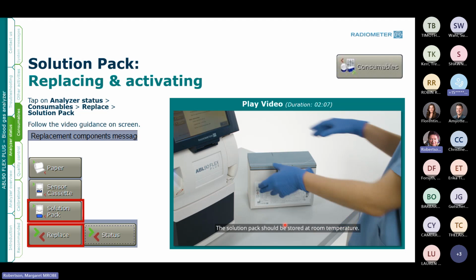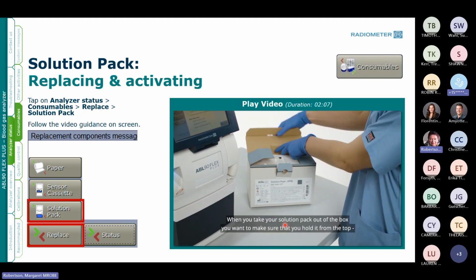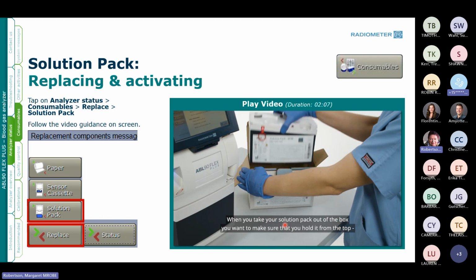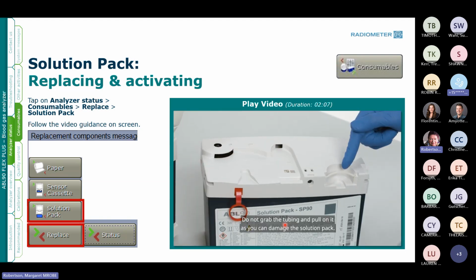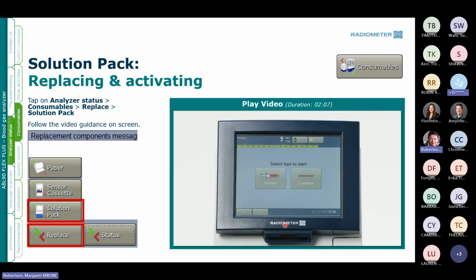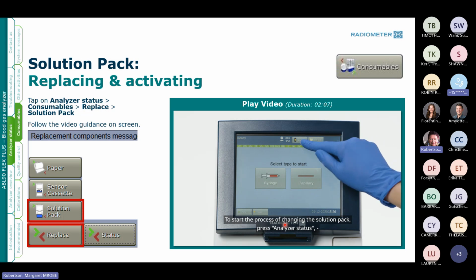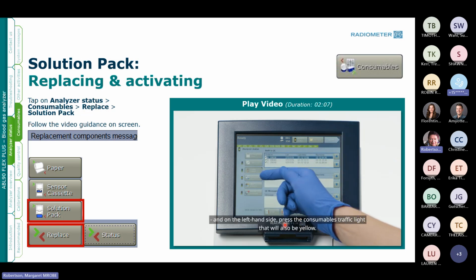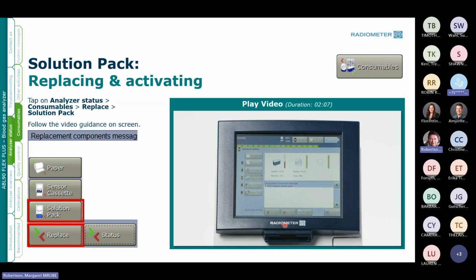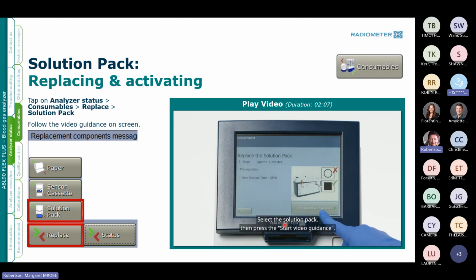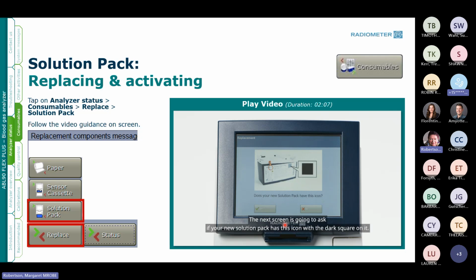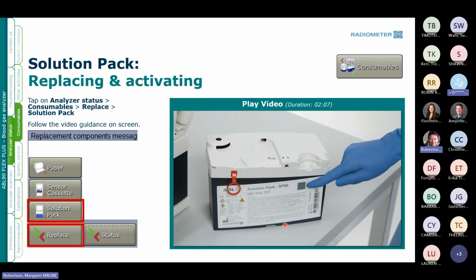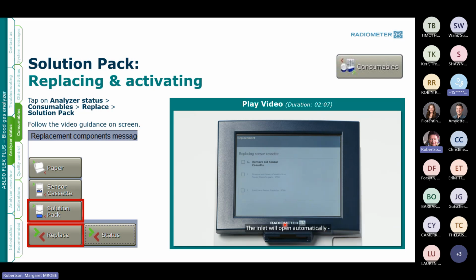Now, the solution pack should be stored at room temperature. When you take your solution pack out of the box, make sure you hold it from the top and then pull it out. Do not grab the tubing and pull on it, as you can damage the solution pack. To start the process of changing the solution pack, press Analyzer Status. On the left-hand side, press the Consumables traffic light that will also be yellow. On the bottom left-hand side, press Replace. Select the solution pack. Then press Start Video Guidance. The next screen is going to ask if your new solution pack has this icon with a dark square on it. Press Yes.